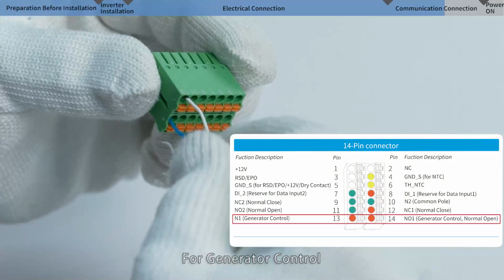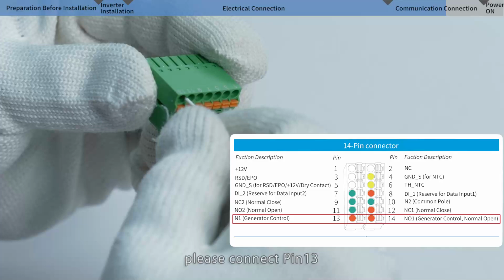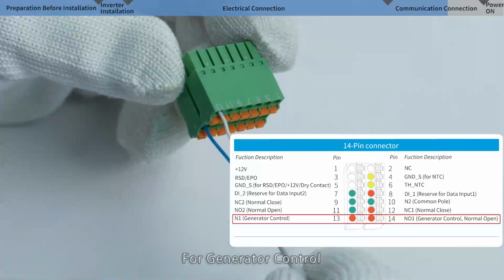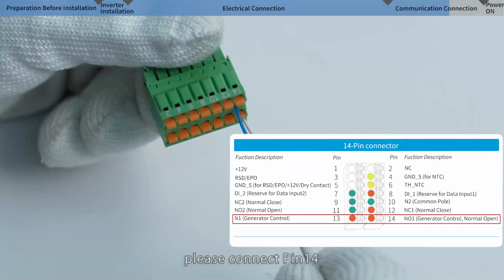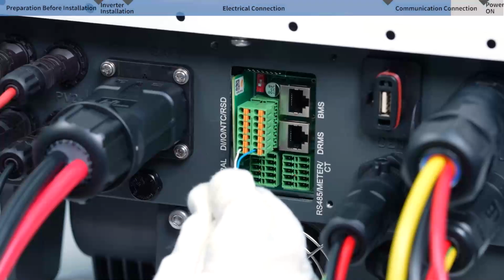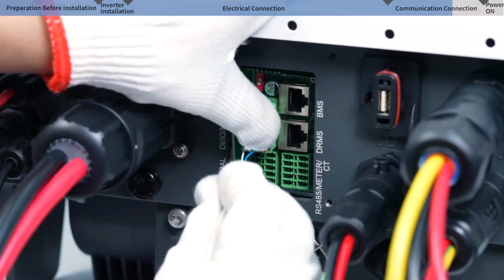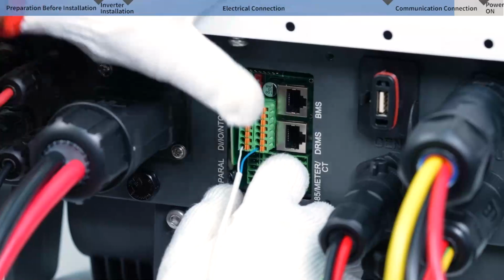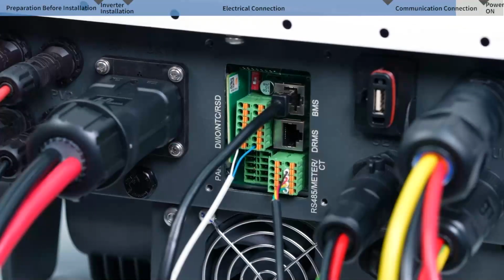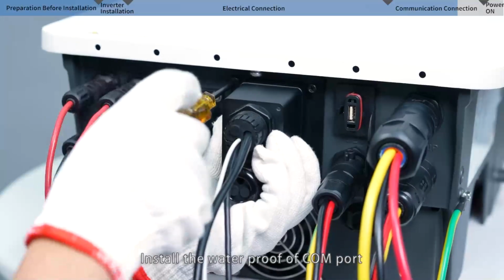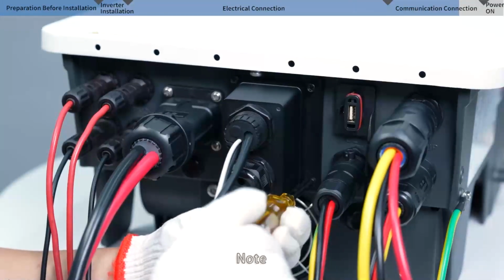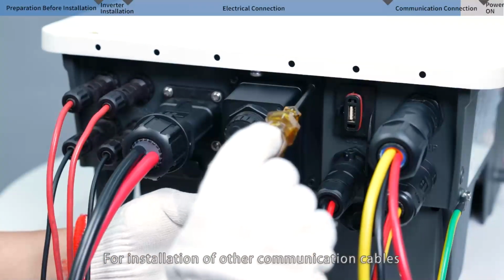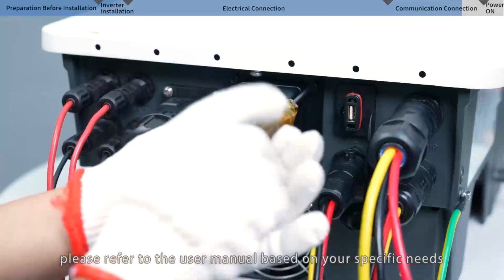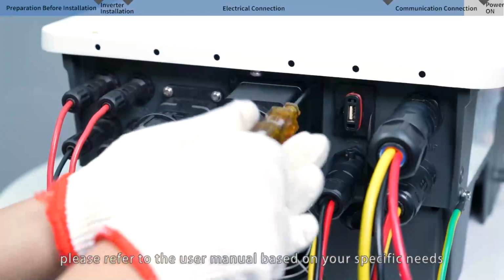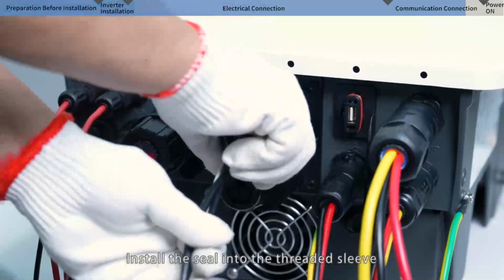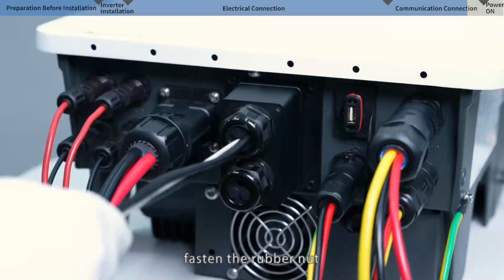For generator control, normal close, please connect pin 13. For generator control, normal open, please connect pin 14. Install the waterproof of communication port. Note, for installation of other communication cables, please refer to the user manual based on your specific needs. Install the seal into the threaded sleeve. Fasten the rubber nut.